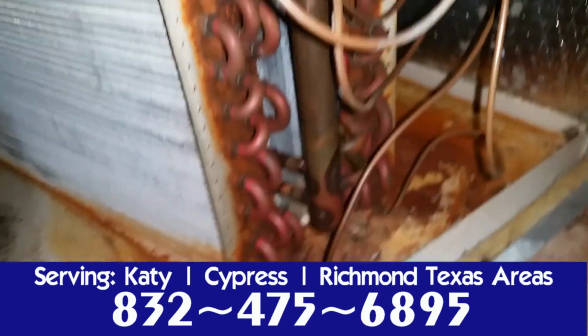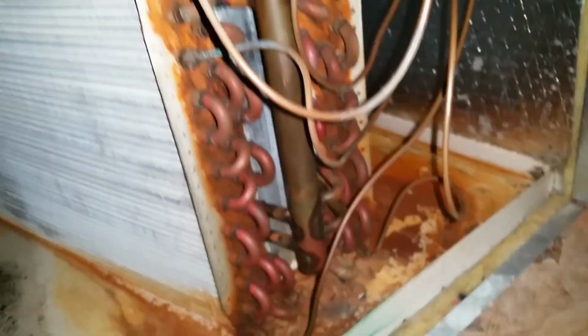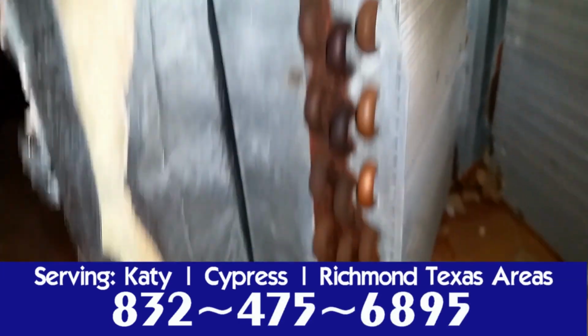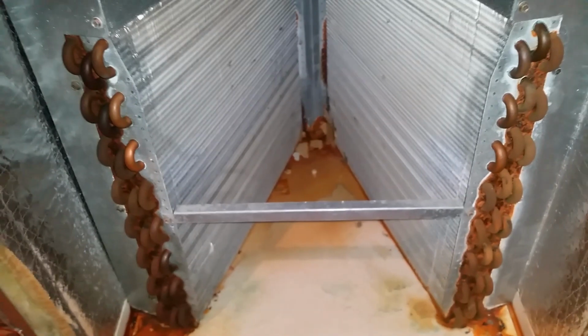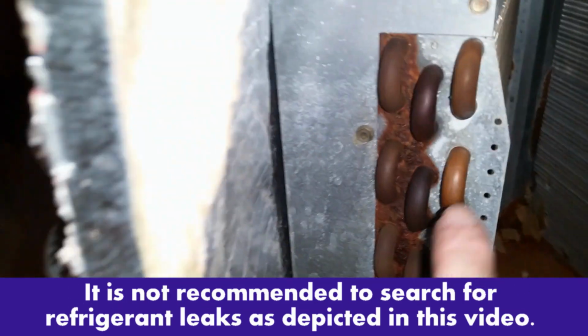This is a coil. You can see that down toward the bottom of the coil, the piping on there is darker, and so that's typically an indication of oil leakage, because the pipe looks stained if you look really close. And you'll notice here that I flip it around and I point to a spot on the coil that I deem a highly likely suspicious part as to where it leaks, and as I noted earlier in the video, it turns out to be a primary leak. You'll see here, I point to it in a minute, because I sit there and I study the coil and I look for the most probable spot where it's probably leaking. You know there's a leak somewhere because the holding charge was very, very low.